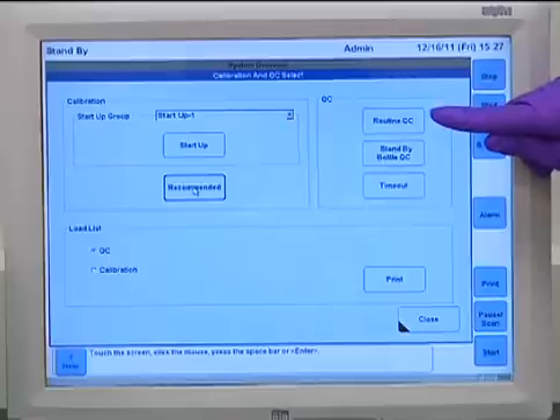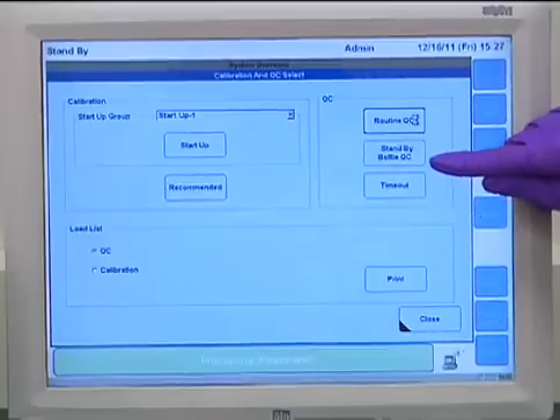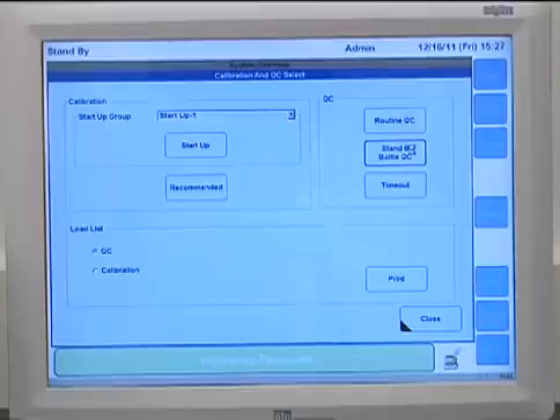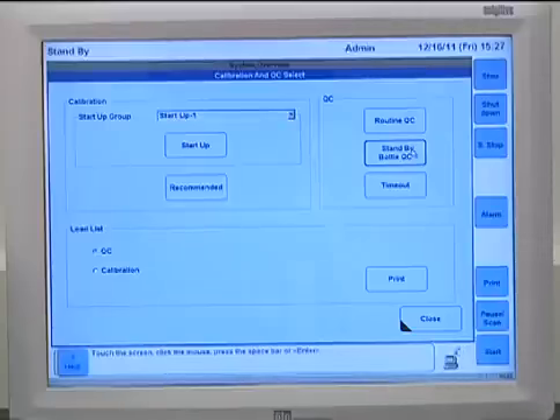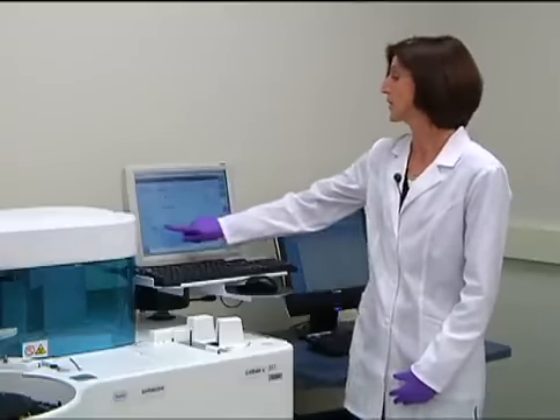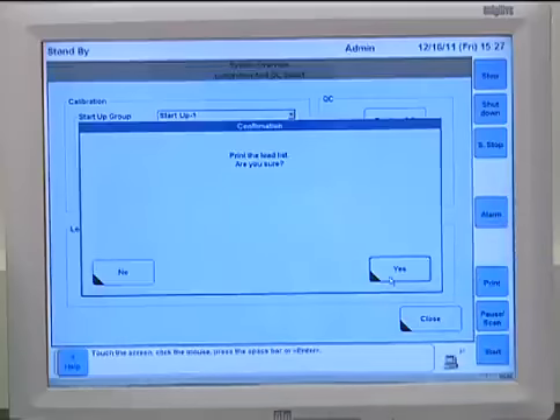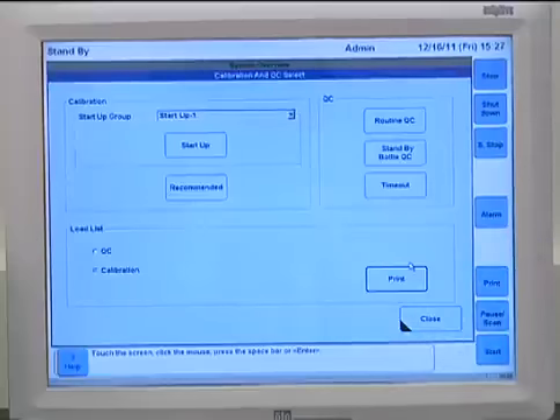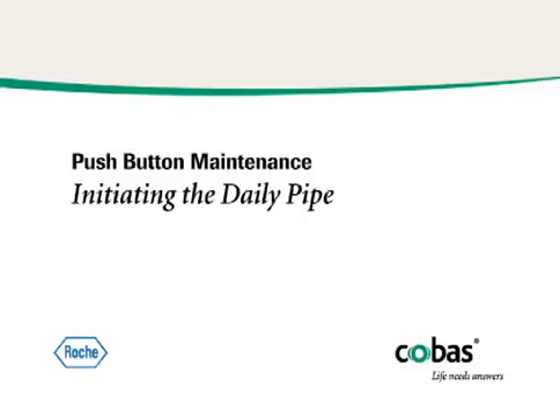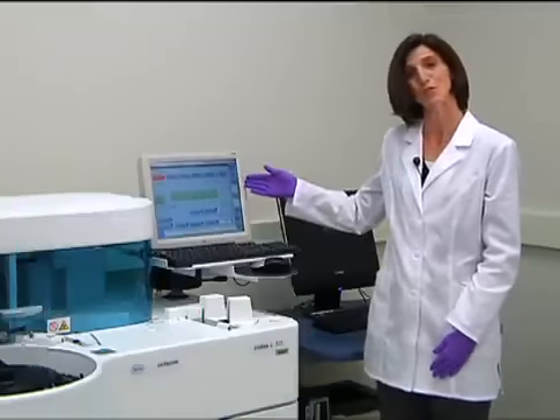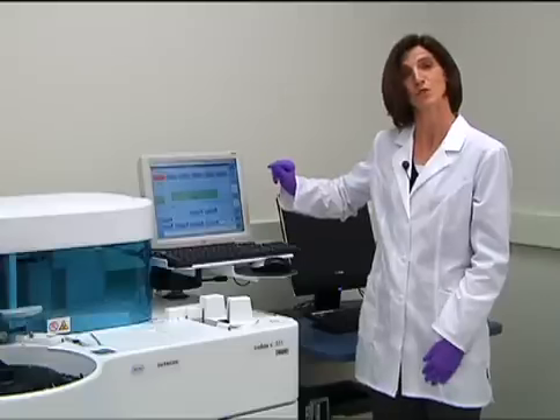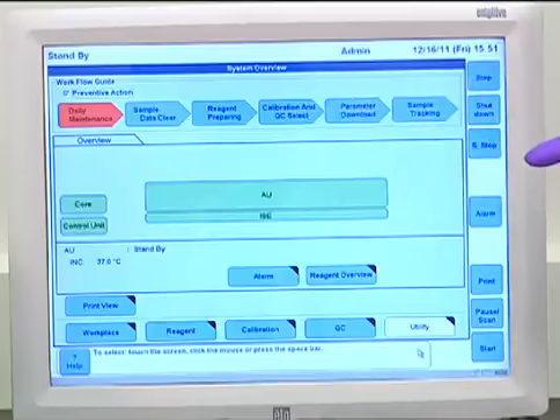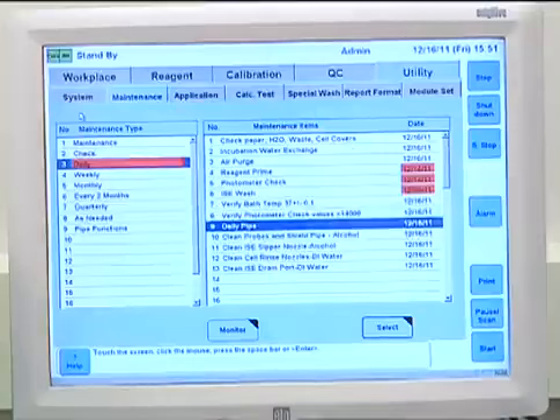Next, I want to order the QC. Selecting two buttons, routine QC and standby bottle QC, will allow us to quickly program QC for all reagents on board, including any standby packs. From this screen, then we're able to print the calibration load list and then the QC load list, which will tell us what materials we need and where to load them. So you can see from our system overview screen that we have taken care of our reagent inventory, we have ordered our calibration and QC, and now we're ready to execute our automated maintenance.